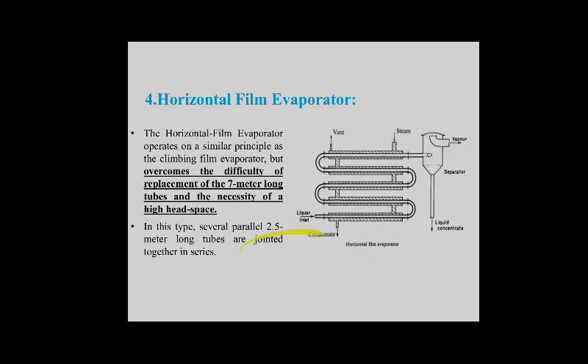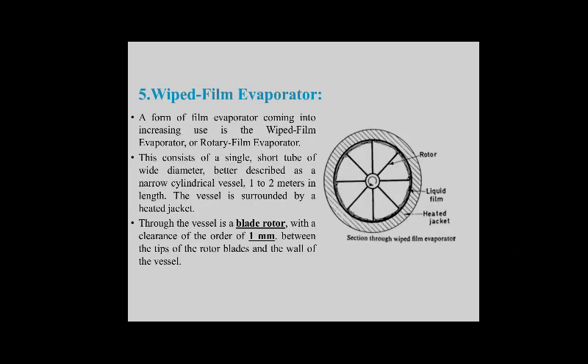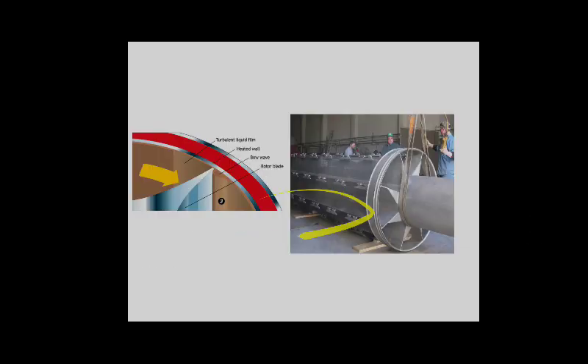The horizontal tube film evaporator operates on a similar principle as the climbing film evaporator but overcomes the difficulty of replacing seven-meter-long tubes and the necessity of high headroom. In this type, several parallel 2.5-meter-long tubes are joined together in series. The wiped film evaporator, also called a rotary film evaporator, is a form of film evaporator increasingly in use. It is used for very viscous liquids.